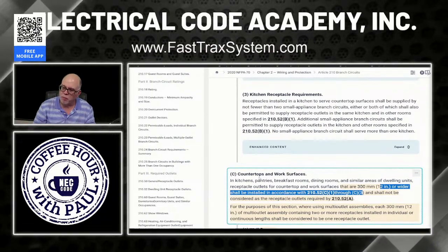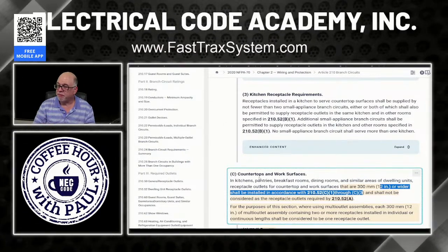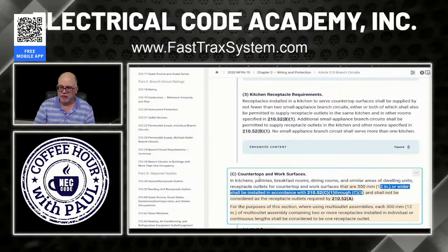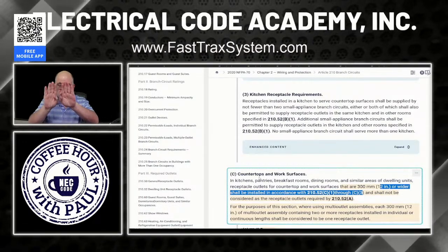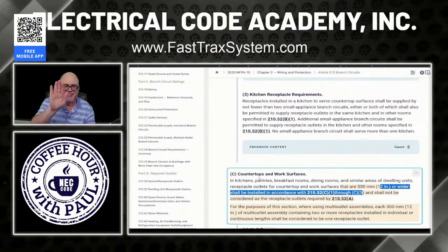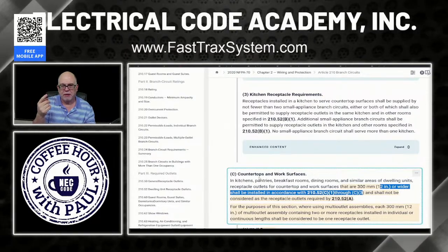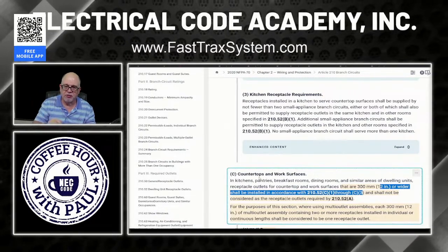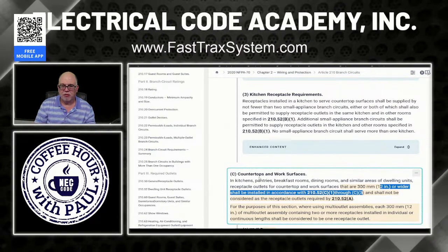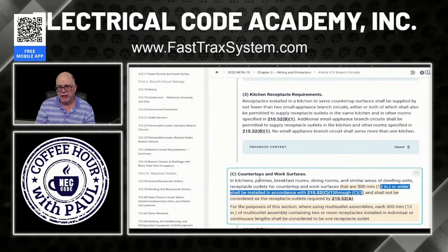Now, somebody says, well, Paul, what if that's my only counter, and I have to have, by the code, a minimum of 2 small appliance branch circuits there. Would I put 2 duplexes there, and one is one circuit and one's the other? Or could I put a duplex receptacle there, break the tab on it, and have the top be one branch circuit and the bottom be the other 20-amp small appliance branch circuit? And the answer to that is absolutely. You could do that if you wanted to.